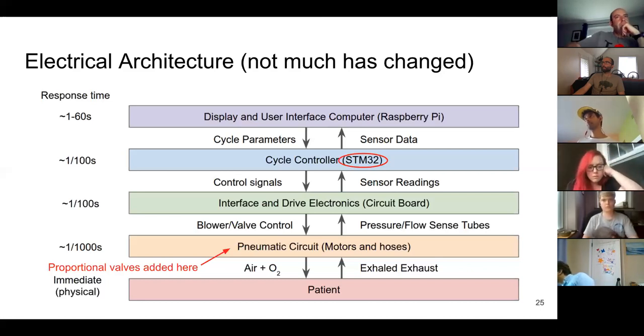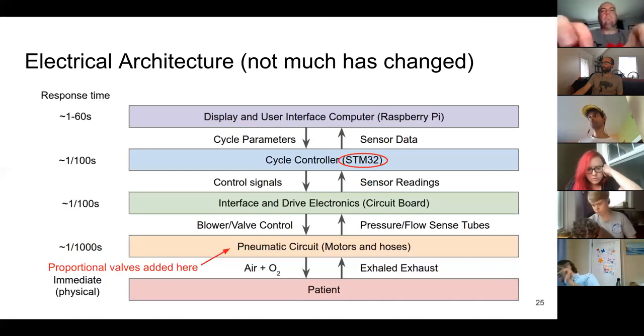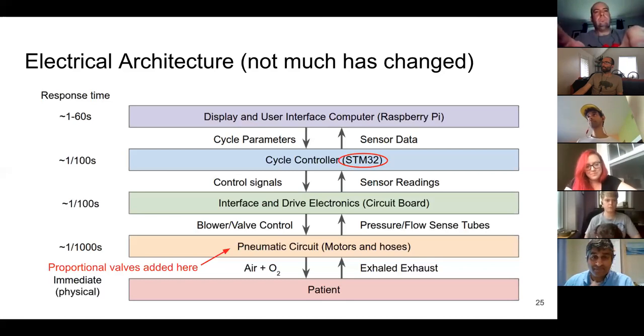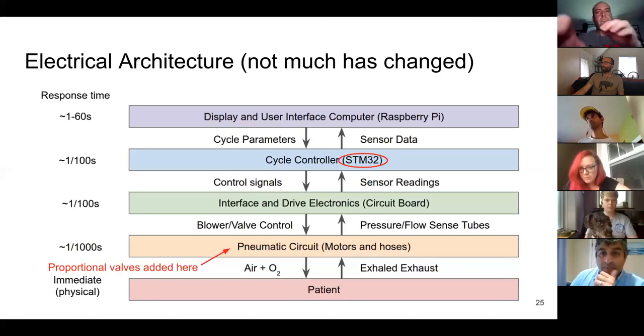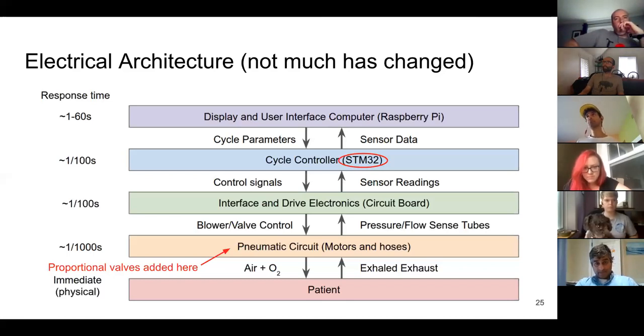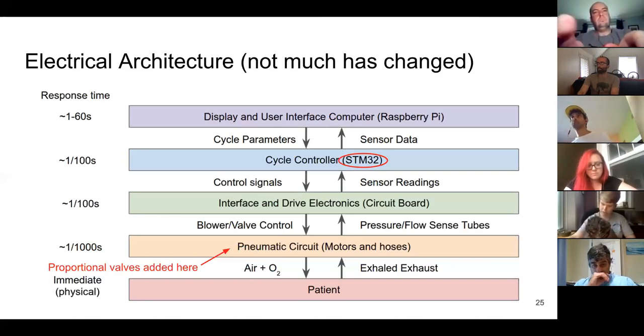So this happens immediately. A way to look at this architecture is by looking at how the response times stack up. The patient operates in real time, then the pneumatic circuit responds in the millisecond range, and then the electronics. The sensors respond on the order of tens of milliseconds, and so the controller needs to do the same. The control unit, which is the STM32 now, responds at a 1/100th of a second rate, and the UI computer responds in the 1 to 60 seconds range, so it's breath-to-breath time. Information is passed at different resolutions between each of these systems.